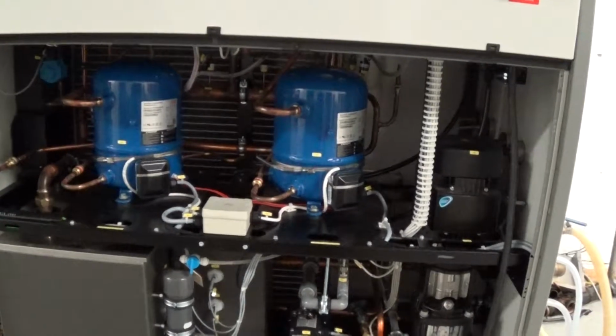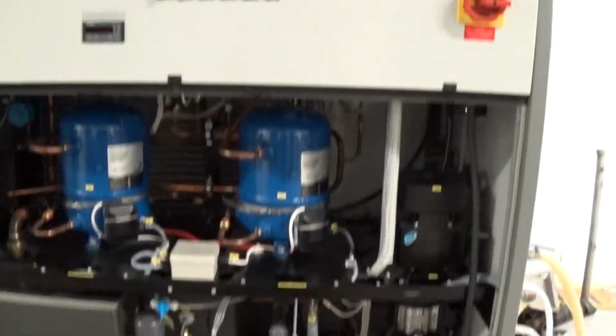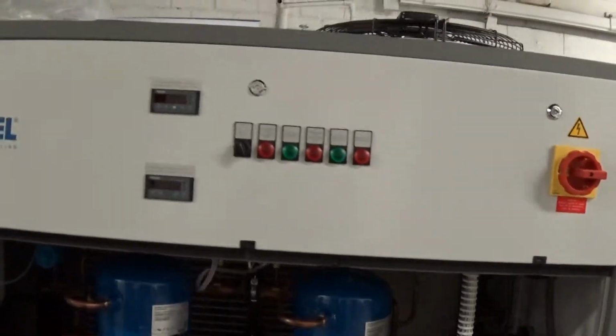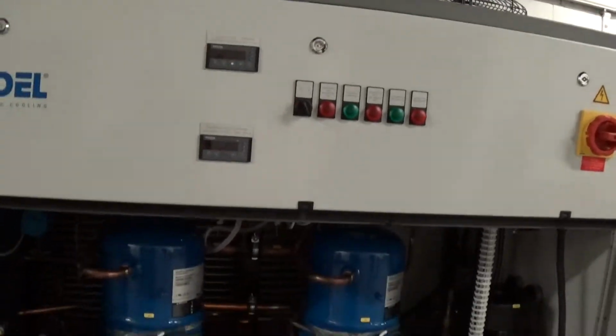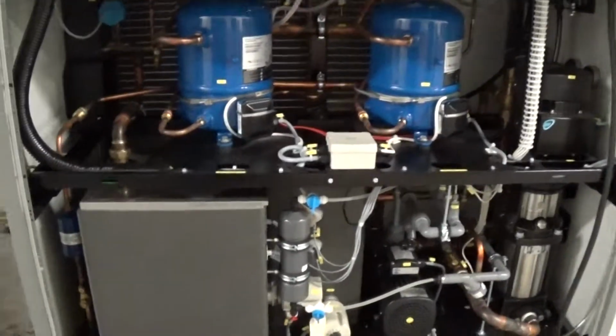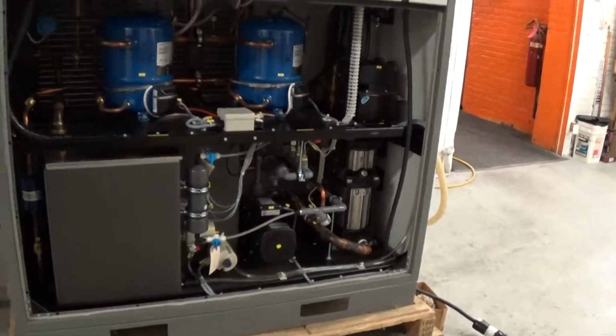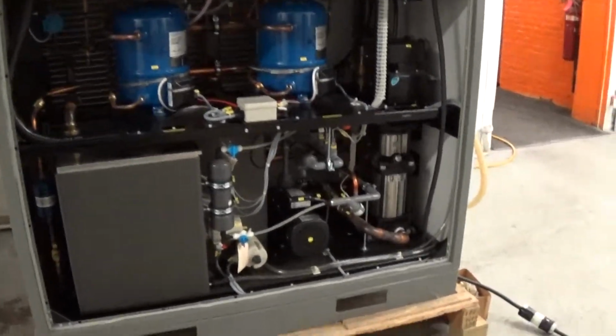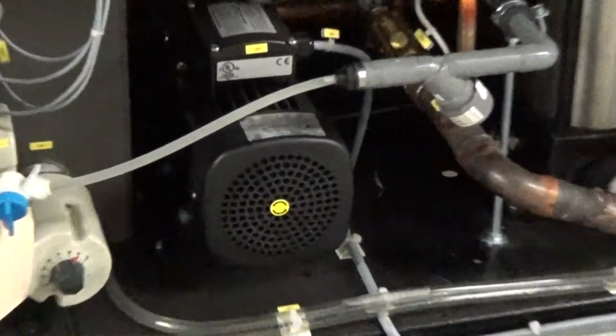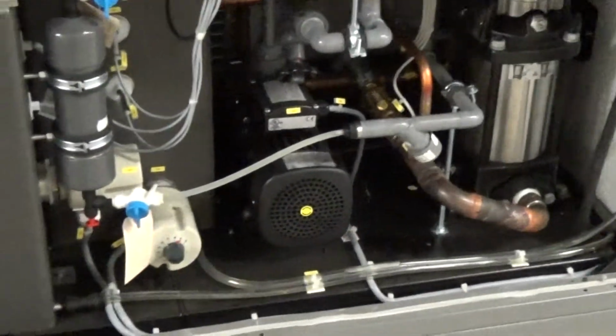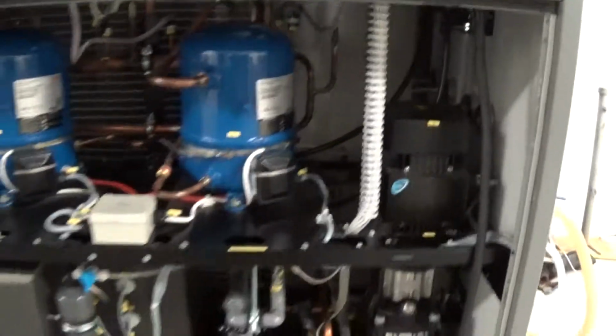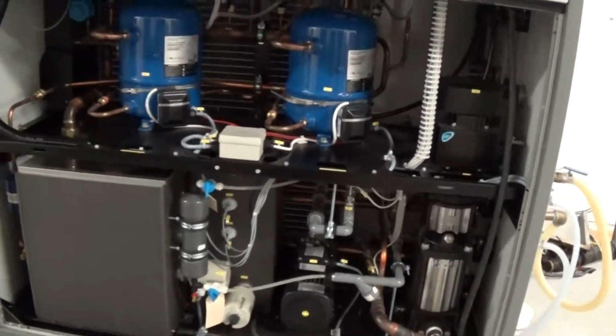These units, and we're going to do just a static kind of runoff or once through here before we put power to the unit. These units are originally set up to cool laser machining. What that basically means is they have a second smaller pump here, and they have a second little heat exchanger right back here that basically steals a little bit of water off the primary main water circuit.